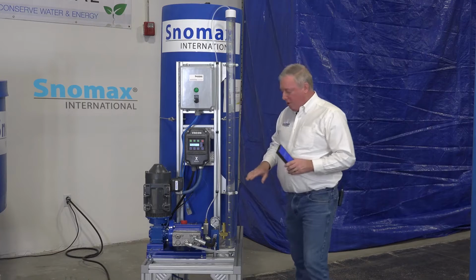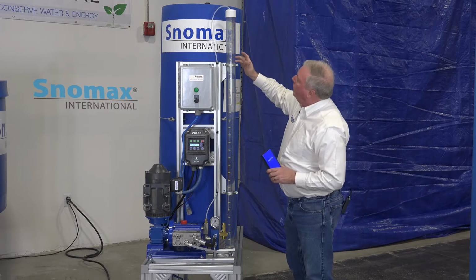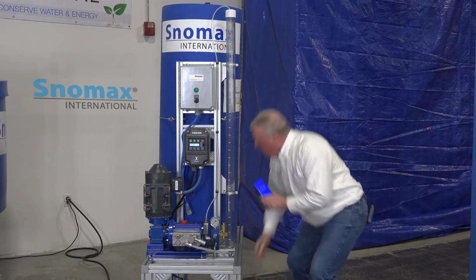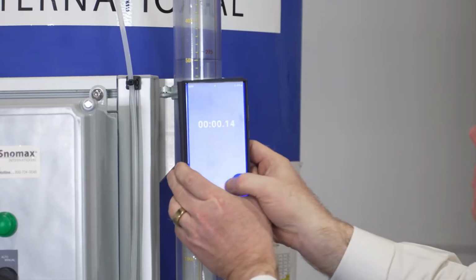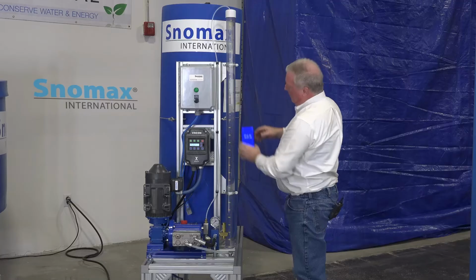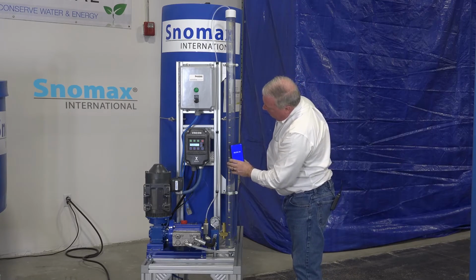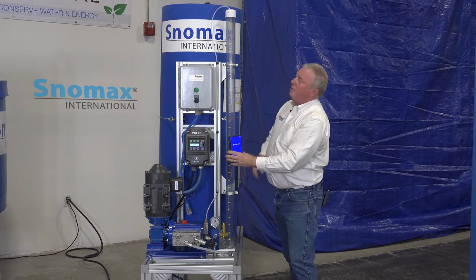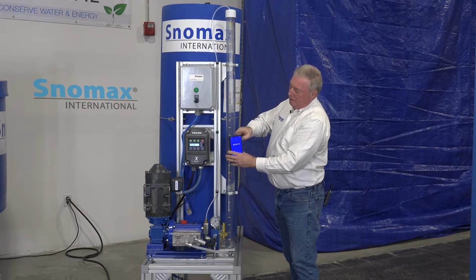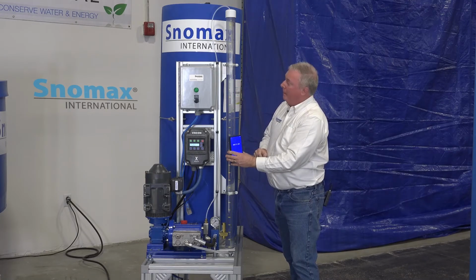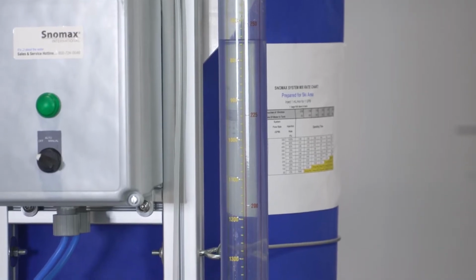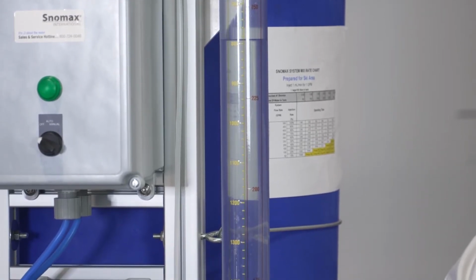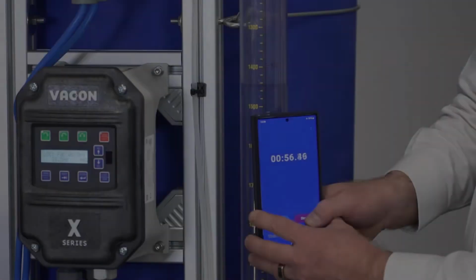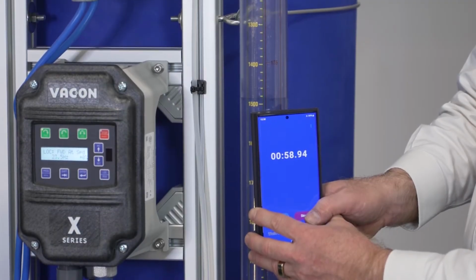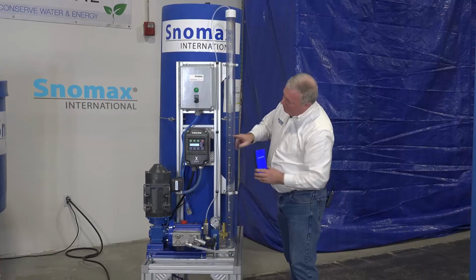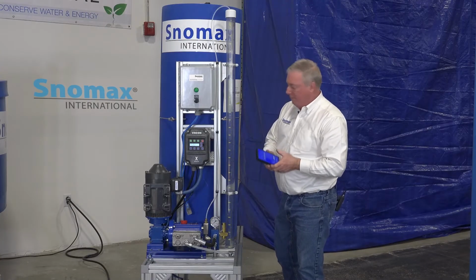All right, so the pump is running a little slower. Now I'm going to look here, we're going to pick the spot, I'm going to close the valve. Start it when it hits 500. And I'm going to hold my phone down here at 15, and we'll see how close we can get this column to be here in exactly 1 minute. And there we're at. We hit the number exactly at 1 minute.